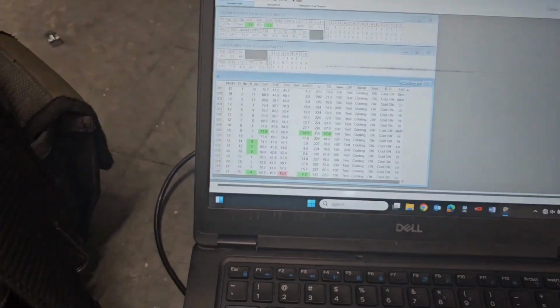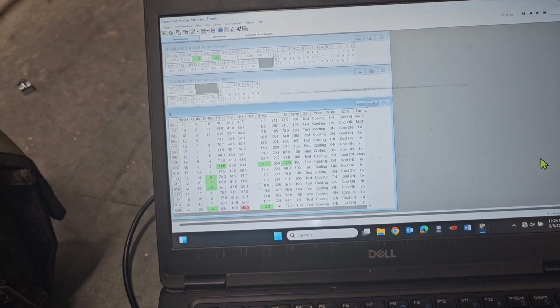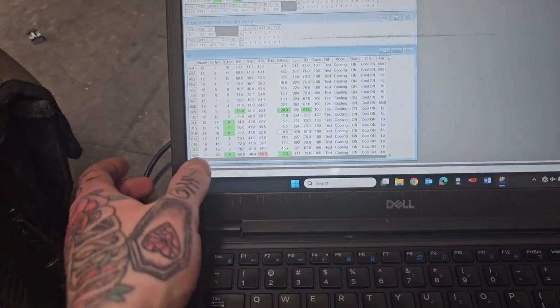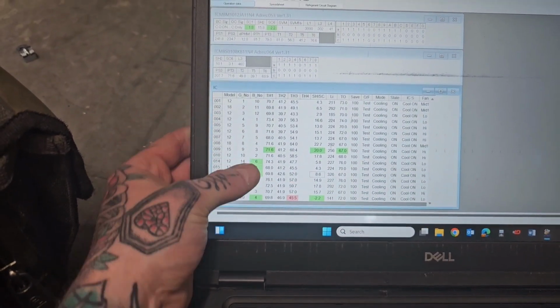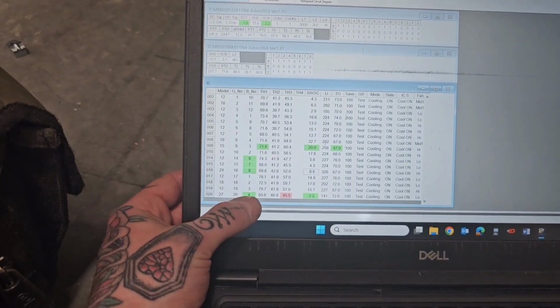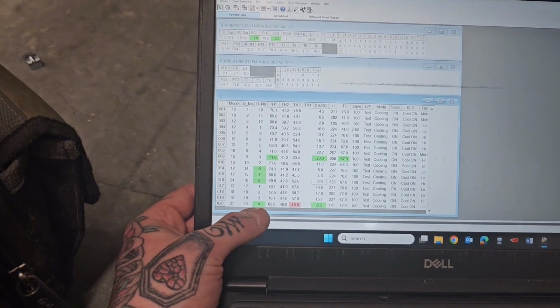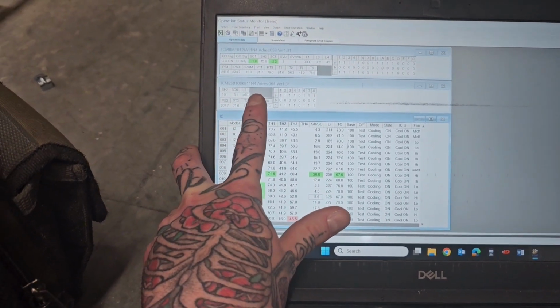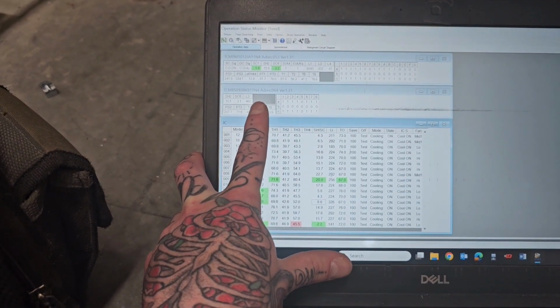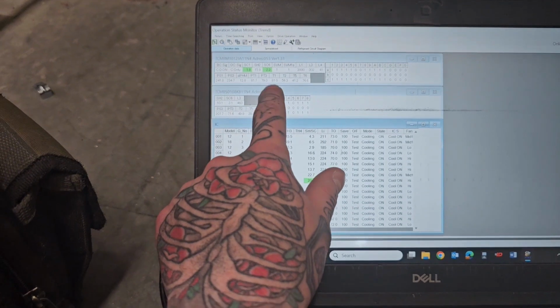So the easiest way to diagnose that is I just went over, found that port, so we can look at our branch number, and these are all the ports that the unit is assigned to. So this one, address 20, is on port 4. In this case, we have a sub branch controller. Sub branch controllers must be addressed correctly.